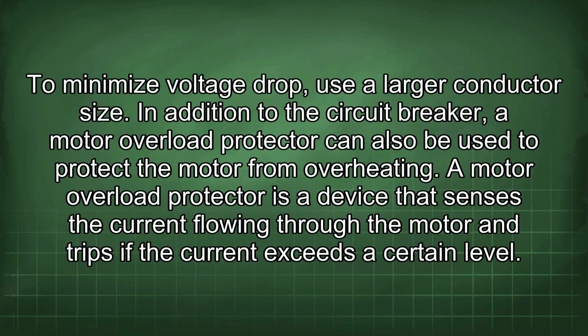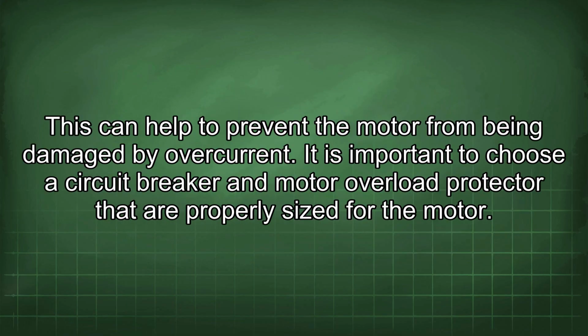In addition to the circuit breaker, a motor overload protector can also be used to protect the motor from overheating. A motor overload protector is a device that senses the current flowing through the motor and trips if the current exceeds a certain level. This can help to prevent the motor from being damaged by overcurrent.